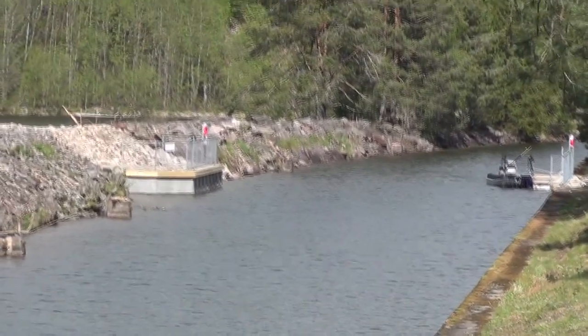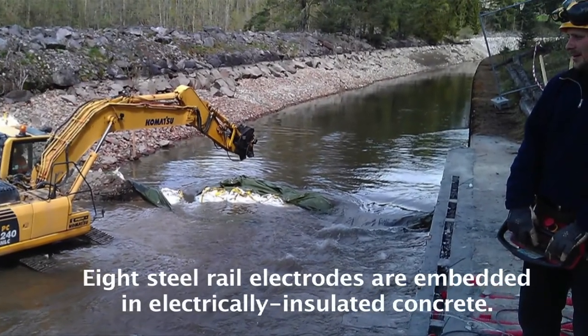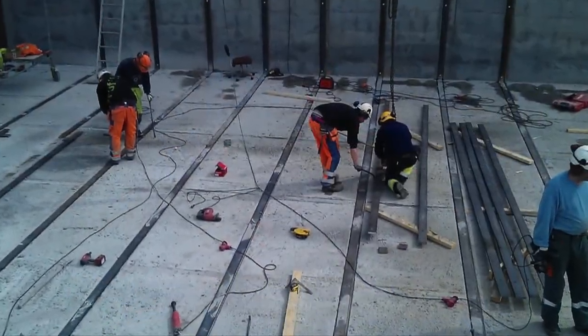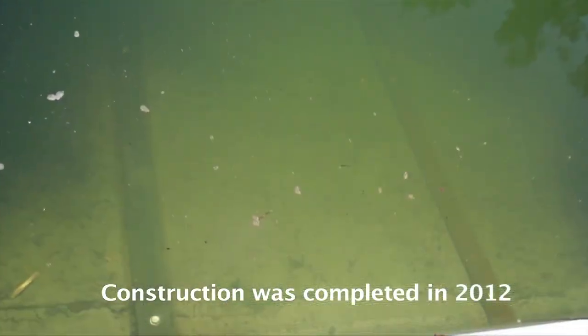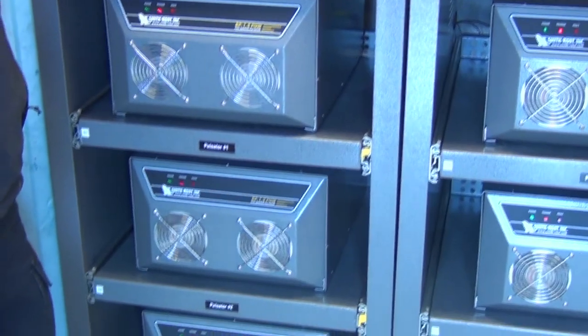You can see we have a number of electrodes down there and we are putting pulsed DC into the water. Now we are inside the control building for the fish barrier. We have 10 active pulsers that are pulsing simultaneously, and one spare pulser that we would switch out if we have a problem.